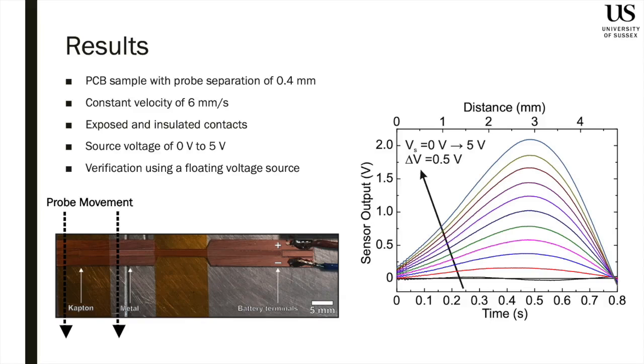non-contact DC measurements. We use the PCB sample as the source under test. The sensor to sample separation in this case was 0.4 millimeter. We moved the sensing probe at a constant velocity of 6 millimeters per second. We did the measurement for both exposed and insulated terminals. The terminals were insulated using Kapton tape in this area, and we had the exposed copper area in this case. We varied the source voltage from 0 to 5 volts. As you can see in the graph on the right-hand side, the sensor output is a function of two different parameters, the time and distance, which are both interrelated depending on the velocity.